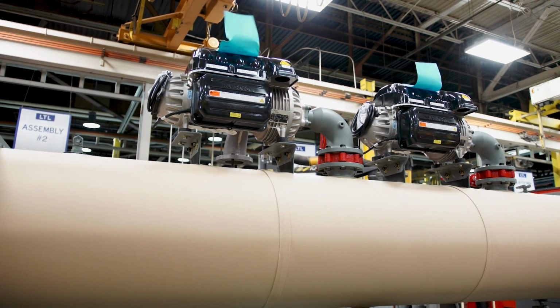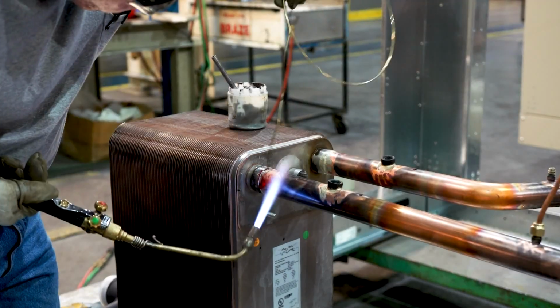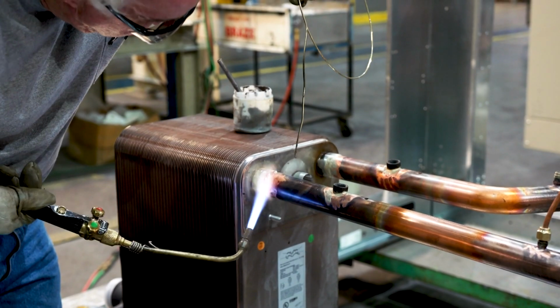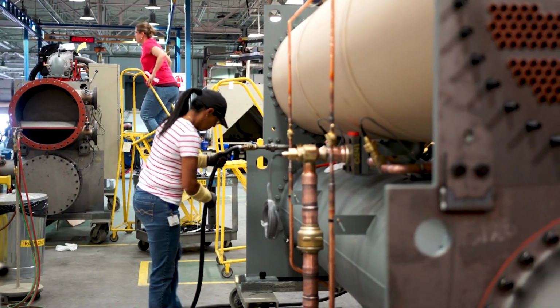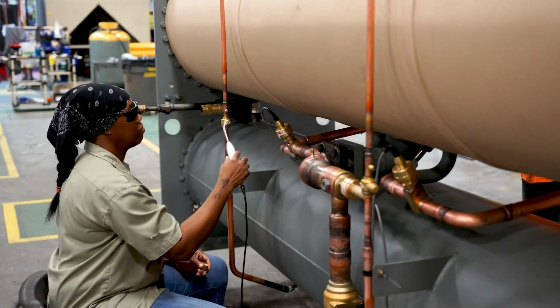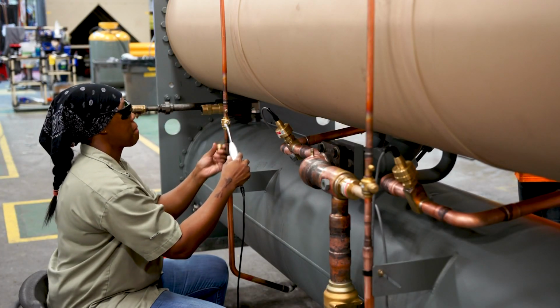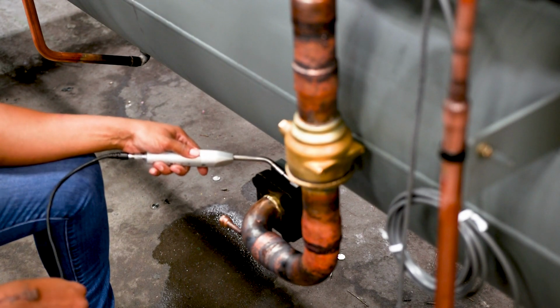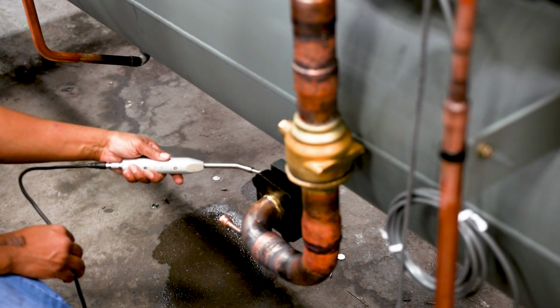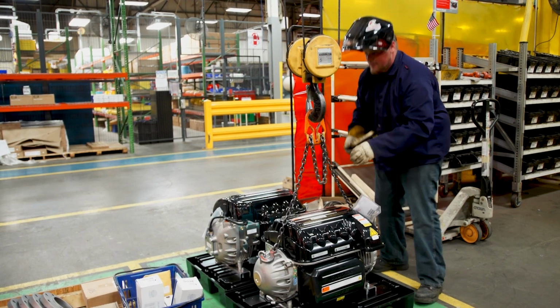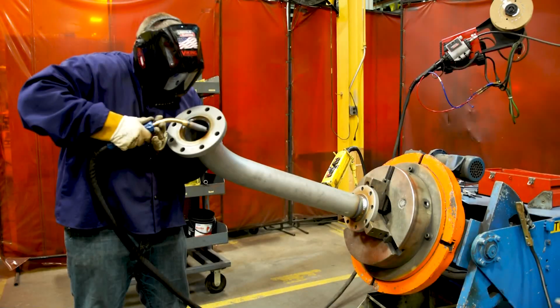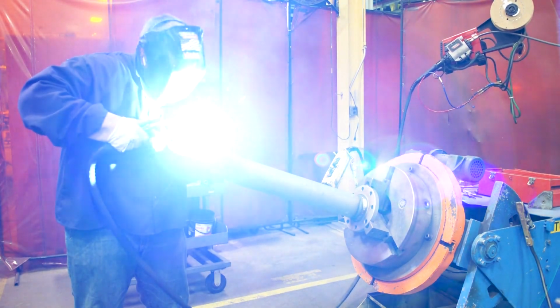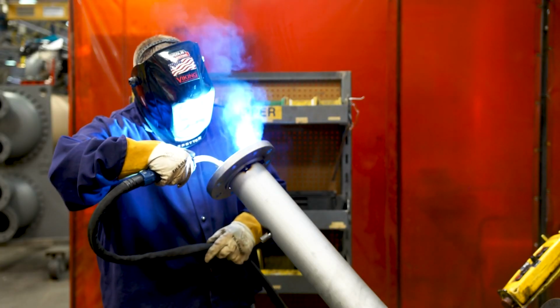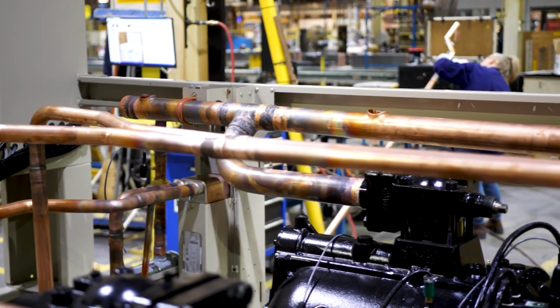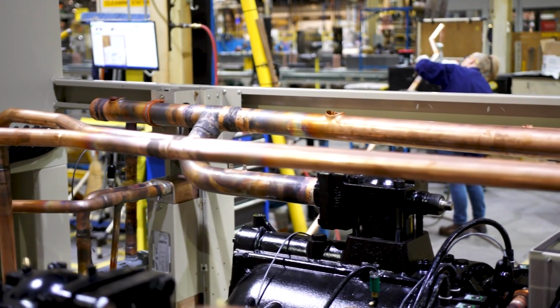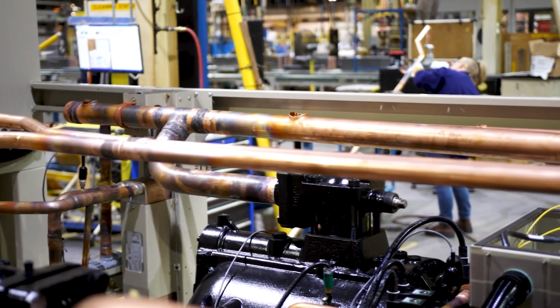The evaporator and condenser is bolted to the vessel. Copper tubing is installed and brazed in place, forming an airtight fit, which is tested by inserting 250 pounds per square inch of nitrogen and checked with a nitrogen sniffer for leaks. The compressor is installed. The flange and discharge pipes are fabricated and welded into place. Copper piping that connects the evaporator, the condenser, heat exchange, and the compressor is brazed into place.